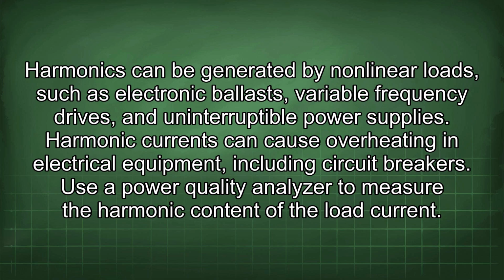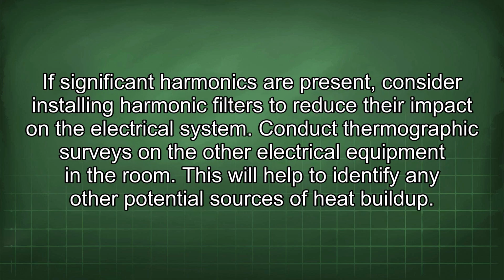Harmonic currents can cause overheating in electrical equipment, including circuit breakers. Use a power quality analyzer to measure the harmonic content of the load current. If significant harmonics are present, consider installing harmonic filters to reduce the impact on the electrical system.